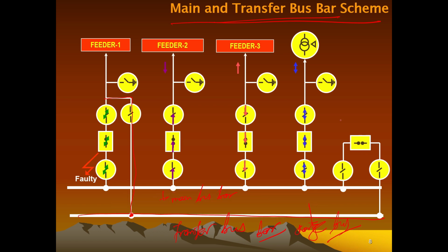So this charging of the bus is required, and we can achieve that by connecting these two buses together, which is through a bus coupler, or in this particular case, the transfer bus coupler. What this transfer bus coupler does is connect these two buses, and once these two buses are connected, both are charged. So now your power flow will be like this. So this is the case.